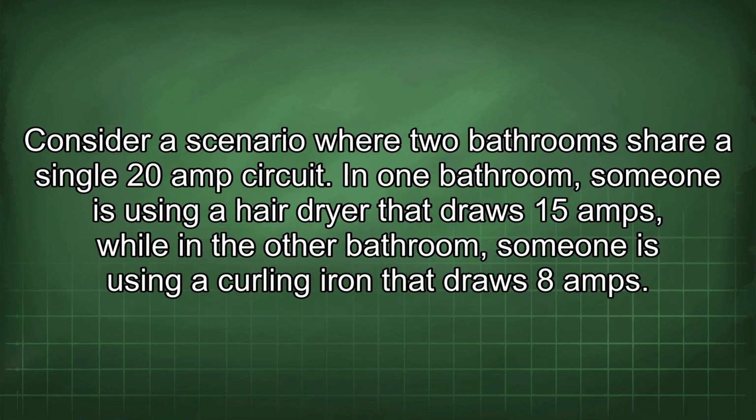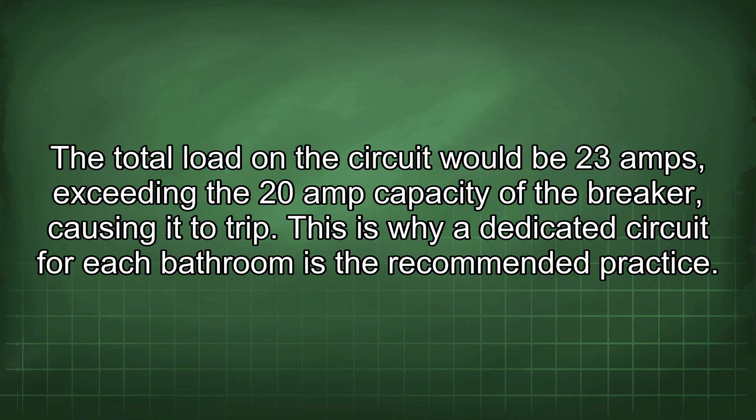Consider a scenario where two bathrooms share a single 20-amp circuit. In one bathroom, someone is using a hairdryer that draws 15 amps, while in the other bathroom, someone is using a curling iron that draws 8 amps. The total load in the circuit would be 23 amps, exceeding the 20-amp capacity of the breaker, causing it to trip. This is why a dedicated circuit for each bathroom is the recommended practice.